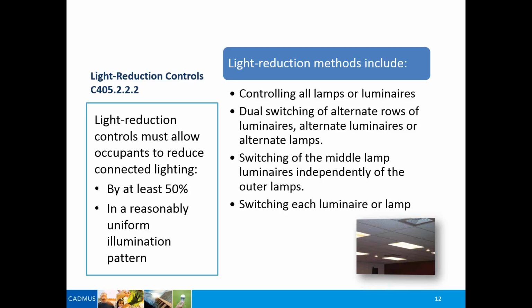So again, the requirements haven't changed, and there's a few options here for the light reduction methods that are included. I know there was an allowance to use a dimmable control in the 2006 code. I believe you can still do that here, just a manual dimming control, if you have a dimmable ballast for those types of fixtures. So that's still a requirement. But the key, again, is uniform lighting reduction. You want to be able to bring the level uniformly down through the entire space, and again, not keep part of the space dark and part of the space light.